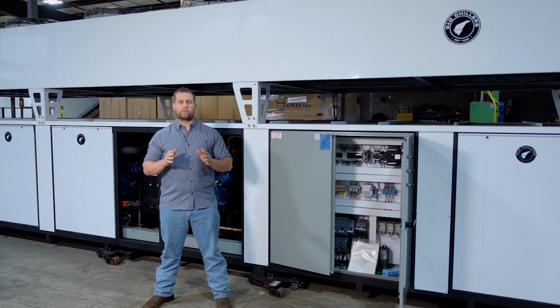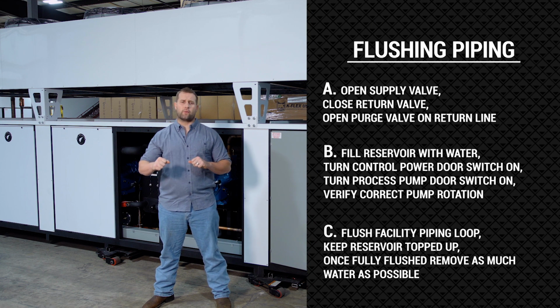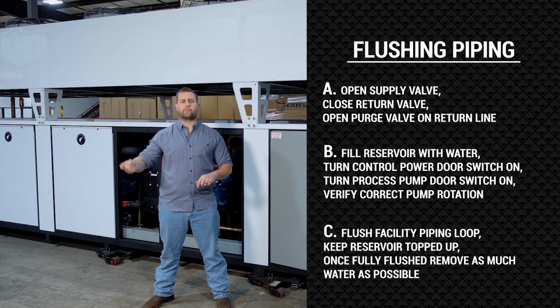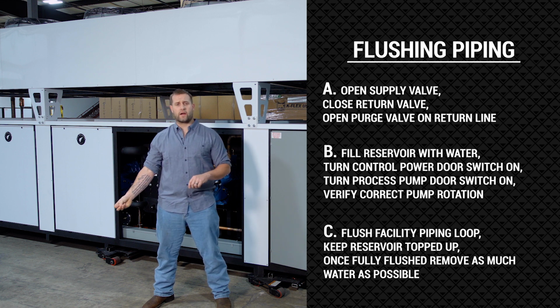The next step on starting this chiller up is flushing your lines. On this unit, you're going to want to fill your reservoir full of water. Make sure you open up your supply valve to your process. You're going to want to close the return valve coming to the chiller, and open up your Y strainer, because you're going to be flushing water throughout your process piping, and it's going to come out of that Y strainer.